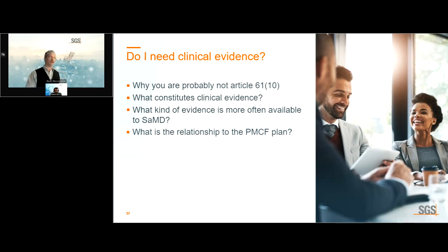Article 61(10), which we'll get into in a moment, is you do not need clinical evidence. You have no clinical benefit. It is outstandingly rare for a medical device to be Article 61(10). I would say approximately 10% of all legal manufacturers try that route. Far less than 1 in 100 of those actually are that route. It is very rare. Now, let's start talking about what constitutes clinical evidence.